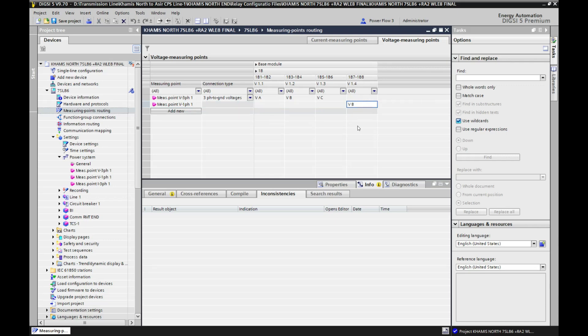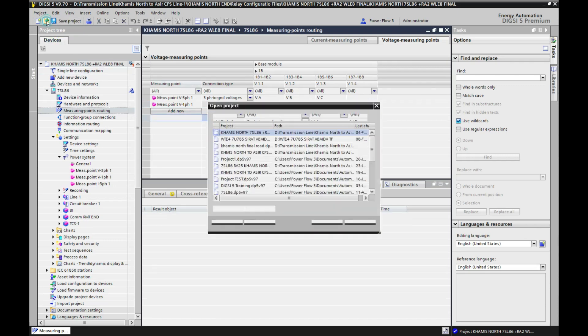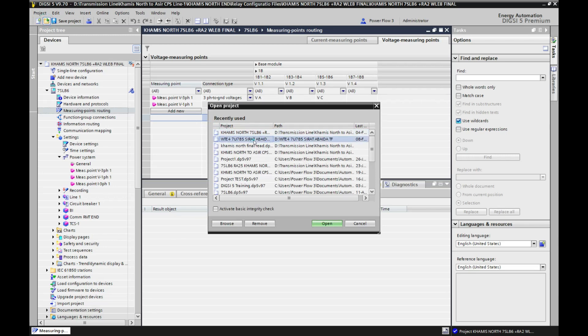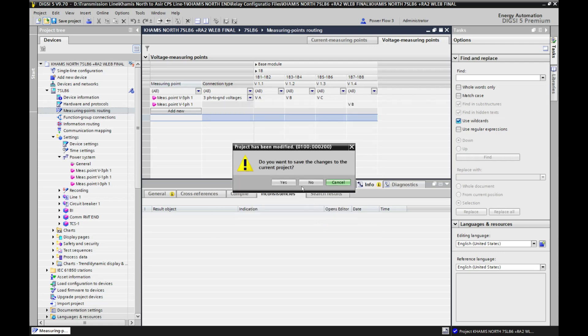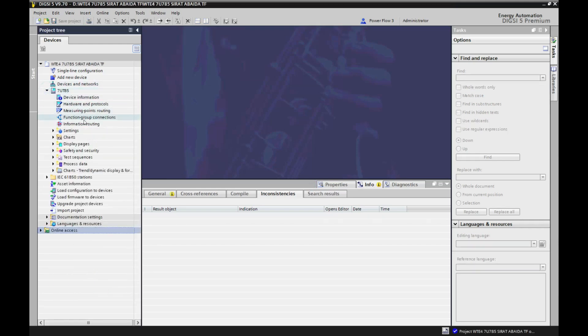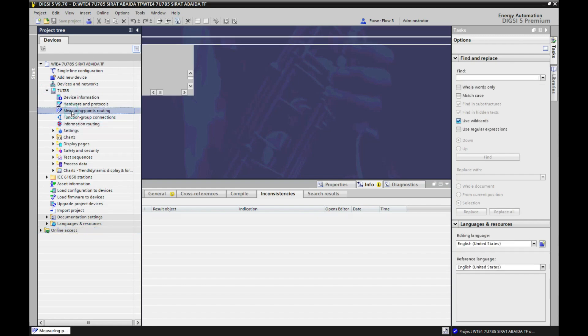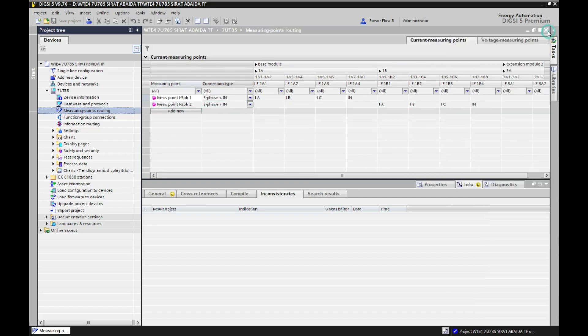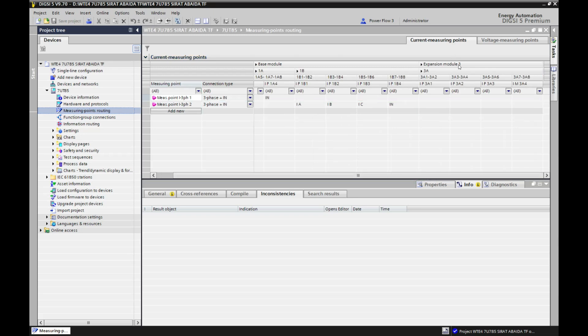I will show you the differential relay measuring point. As you can see, more current and voltage channels are available — not many voltage but more current channels, because for differential we need a minimum of two or three. I go to measuring point routing. The current channels are available in the base module: one A complete channel, one B complete channel, and another CT available in the expansion module at position number three. Coming from the left side, we have first module, second module, and third module — three A means the third module, which also has one channel available. So here we have three current channels available.